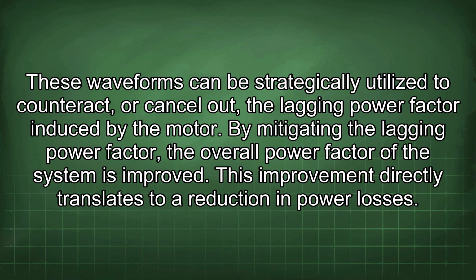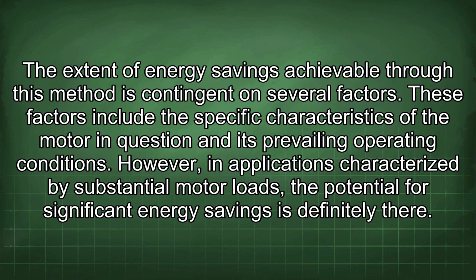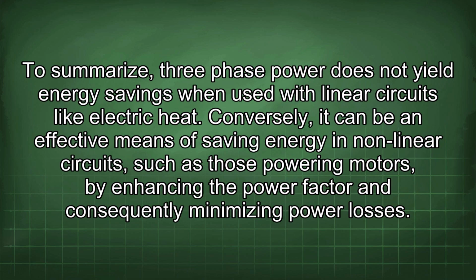By mitigating the lagging power factor, the overall power factor of the system is improved. This improvement directly translates to a reduction in power losses. The extent of energy savings achievable through this method is contingent on several factors. These factors include the specific characteristics of the motor in question and its prevailing operating conditions. However, in applications characterized by substantial motor loads, the potential for significant energy savings is definitely there. To summarize, three-phase power does not yield energy savings when used with linear circuits like electric heat. Conversely, it can be an effective means of saving energy in nonlinear circuits, such as those powering motors, by enhancing the power factor and consequently minimizing power losses.